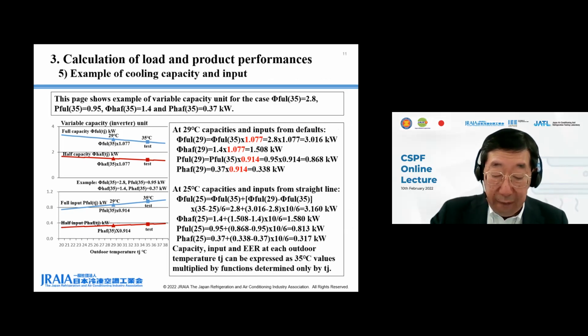Because 29 degrees C full capacity in the equation of the straight line is 35 degrees C full capacity multiplied by default 1.077, the equation can be expressed as 35 degrees C full capacity multiplied by a function of outdoor temperature Tj, which is 25 degrees C in this case. In the same way, half capacity, full input, and half input at each Tj can be expressed as 35 degrees C value multiplied by function determined by only Tj. Accordingly, full and half EERs at each Tj also can be expressed as 35 degrees C value multiplied by function determined only by Tj.